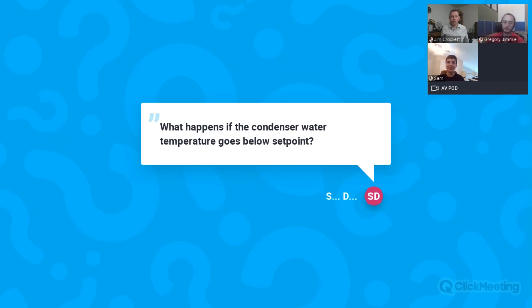What happens if the condenser water temperature goes below set point? Okay, well, condensing water is going to be on your cooling towers, right? So kind of getting into that same conversation, you want to modulate the fans to maintain that set point. Realistically, you don't want to go below what the manufacturer says. In most cases, their answer will be that it's a lift requirement on the compressor.